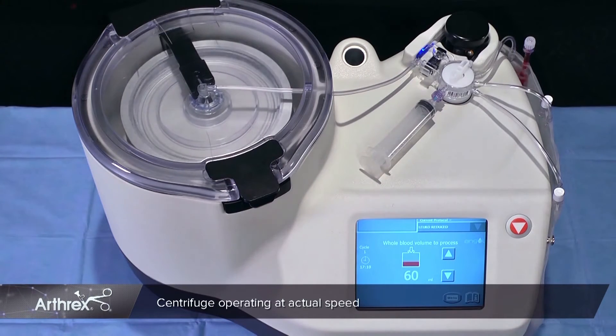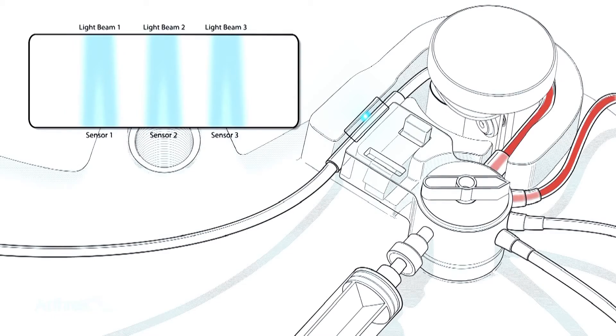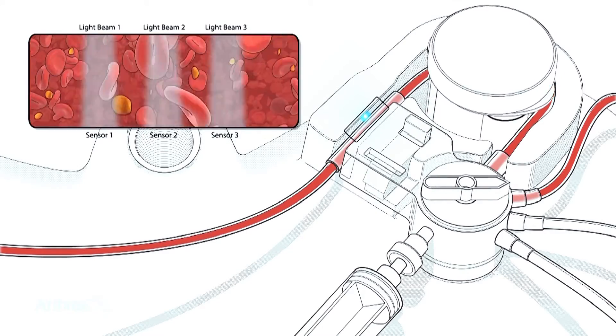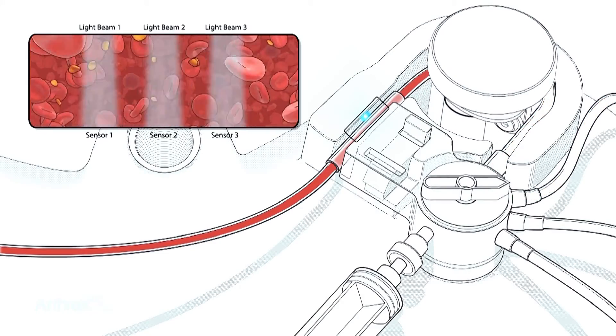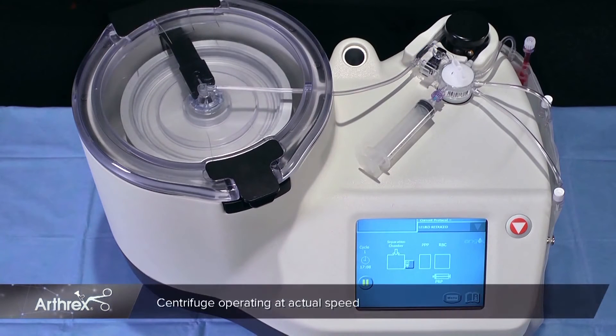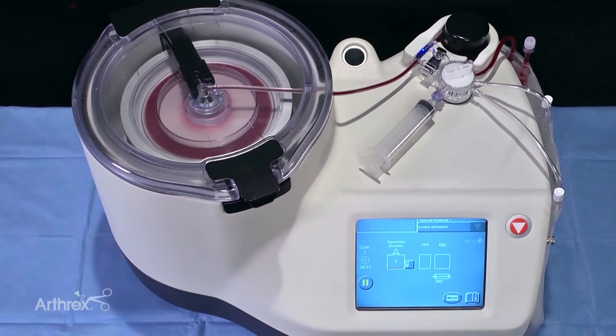As blood is drawn from the whole blood reservoir and loaded into the separation chamber, it will pass through the platelet sensor. The Angel incorporates three sensors to separate blood components using cell specific wavelengths of light. The Angel can process 40 to 180 milliliters of whole blood in a single cycle. The Angel will automatically adjust spin times and speeds when volume and hematocrit values are changed. The adaptive spin technology utilized by the Angel system ensures optimal platelet recovery.